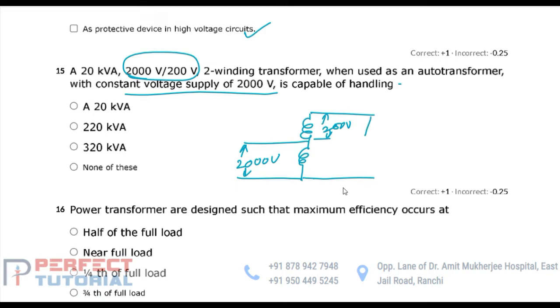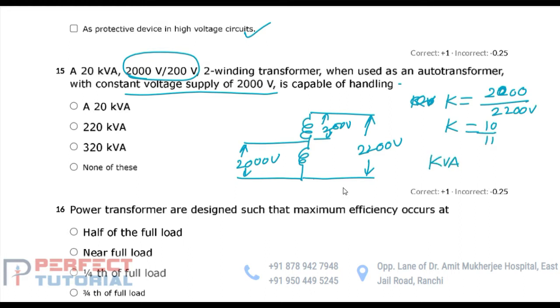Now this is the HV side voltage rating of the ATR and this is the LV side voltage rating of the ATR. So the K value of the ATR is given as 2000 divided by 2200 volt. This is your LV and this is your HV. So K is equal to 10 by 11. Now you know the kVA rating of the ATR is equal to 1 by (1 minus K), that is 1 by (1 minus 10 by 11), multiplied by the kVA rating of the two winding transformer. Here you take 20 kVA and it would give you 220 kilovolt ampere.